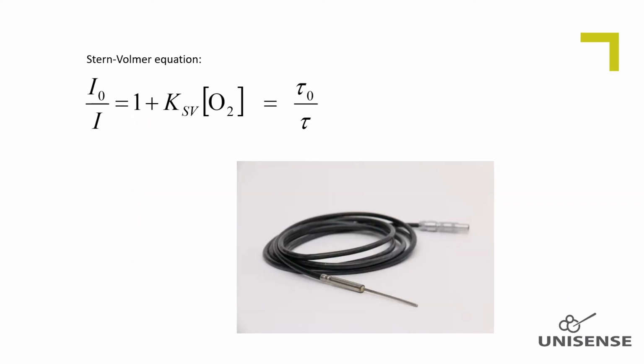The Stern-Volmer constant is temperature dependent. Thus, the phase shift is also temperature dependent. However, this temperature dependency can be determined and will be the same for all optodes. With this determined temperature coefficient, the optodes can be temperature compensated, provided that the temperature is measured continuously and that the measured temperature reflects the temperature at the optode tip correctly. We recommend, however, to calibrate at a temperature not far away from the measuring temperature.